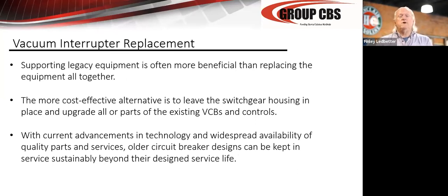The vacuum interrupter replacement. We talked earlier about how it's very easy to keep the switchgear in service 100 years. It's just steel. The bussing inside can be cleaned and retorqued. It's just copper. You can replace the instrument transformers, the control wiring, and upgrade the relaying pretty easily. There's all kinds of modern relays that are just wonderful. I'm not a proponent of that. I'm still an old electromechanical guy, but you can't underestimate the efficiency of modern solid-state relays. So you can basically keep the switchgear in service because relays, potential transformers, and wire are available. The actual structure is steel and copper.